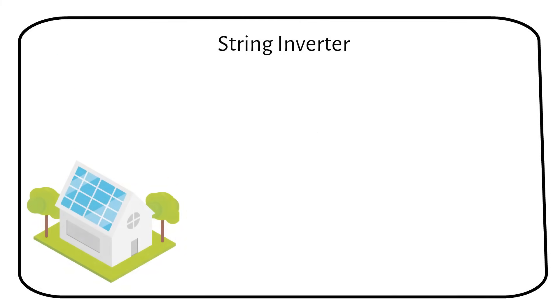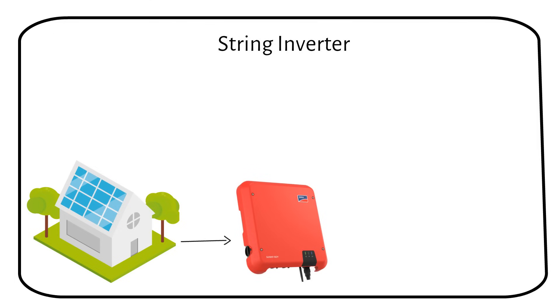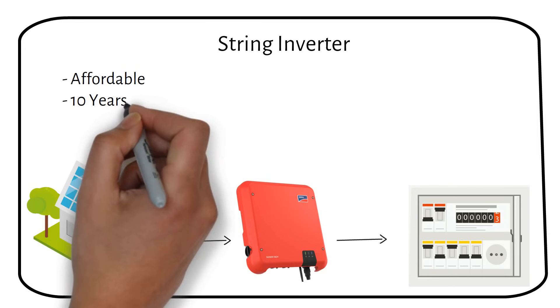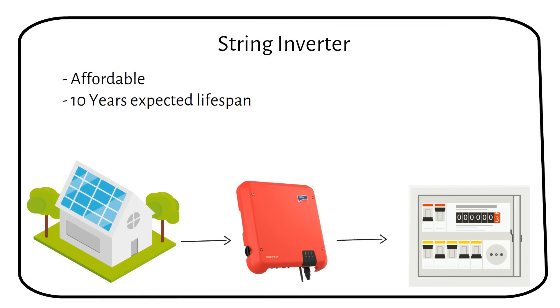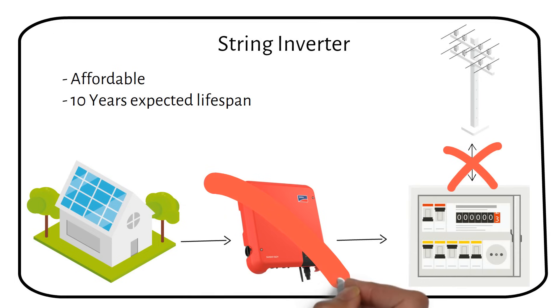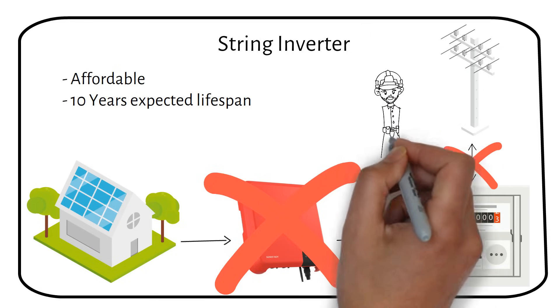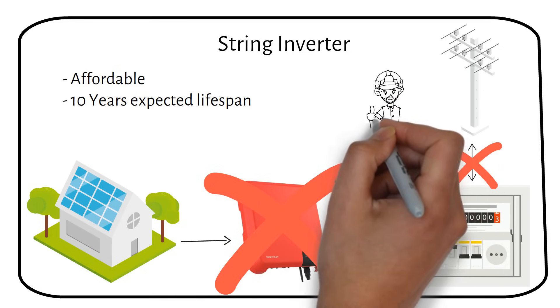A string inverter links solar panels together in a line or a string and transforms their power into AC, which we can use in our homes or send back to the grid. This kind of inverter is common in homes because it's affordable and straightforward. Its expected lifespan is about 10 years, making it a good choice for grid-tied solar power. However, this inverter must be connected to the grid — if there's a problem with the grid and it stops working, the string inverter will turn off to keep people who might be fixing the grid safe, so they don't get shocked by unexpected electricity from the solar panels.